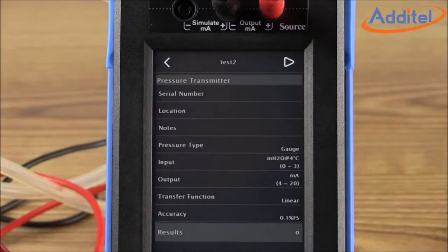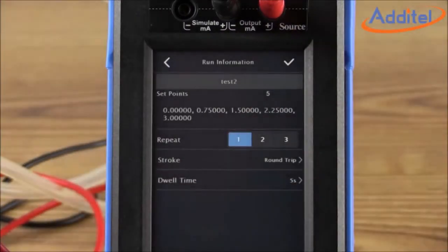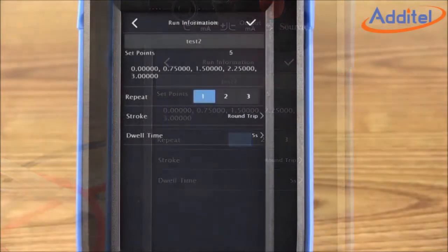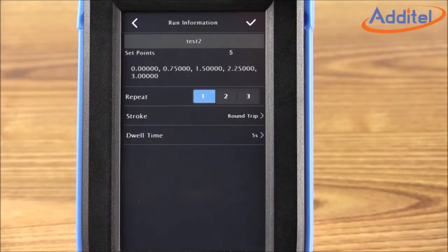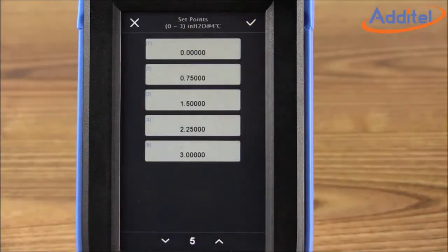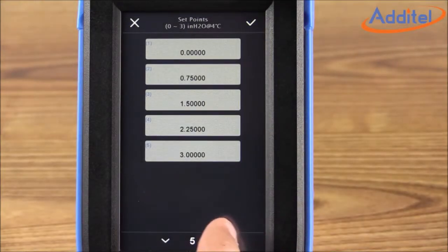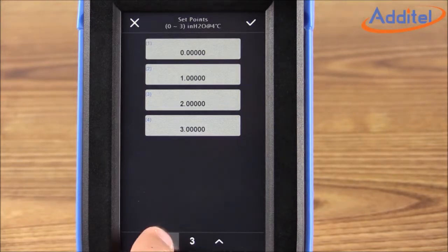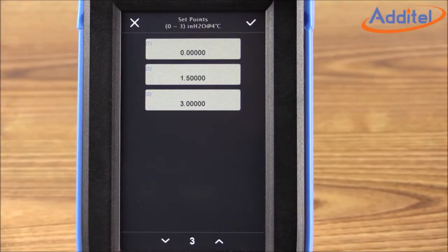We'll see a brief summary of the test we're about to start. We initiate the testing process by clicking the play button in the upper right corner. From the Run Information screen, we can select the number of set points we'd like to collect data for, as well as a few other test parameters, such as the stroke and dwell time. The number of calibration points and their values can easily be adjusted by clicking on the set points and using the up and down arrows to increase and decrease the number of calibration points across the range of the calibration.